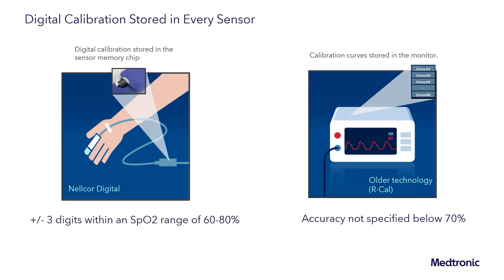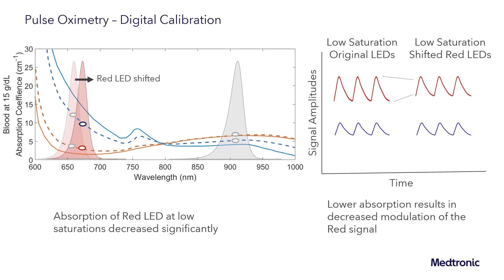The last example that we will walk through is employing digital calibration. Nellcor employs digital calibration on the sensor memory chip. By doing that, Nellcor is able to achieve an accuracy specification of plus or minus three digits within the range of 60 to 80%. That's contrasted with older technology where that calibration curve had to live on the monitor. To understand why Nellcor is able to achieve higher accuracy than older technologies, we can go back to our fundamentals of pulse oximetry where we had talked about looking at those absorption spectra of blood. We have two different cases: a low saturation case shown as the blue dashed line, and a high saturation case shown as the red dashed line.